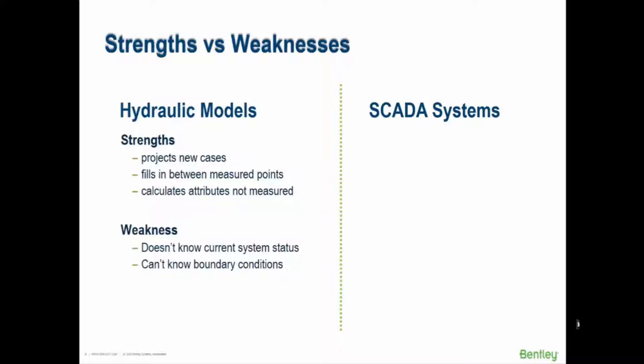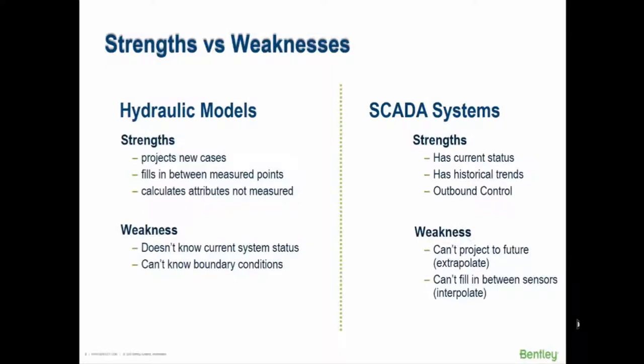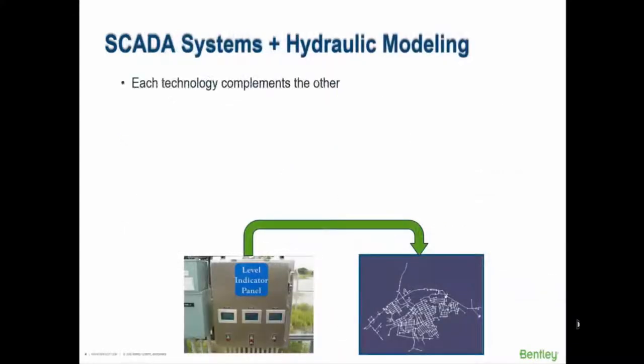The problem with models is they don't know what's going on right now, so you can't bring in live boundary conditions or initial conditions for a model run. The SCADA system, on the other hand, knows what's going on right now and what went on in the past. However, it can't project to the future, and it can't fill in between sensors — if you have 20,000 nodes in your model, you may have only 20 monitoring points. So the SCADA system and models each have strengths and weaknesses. Let's put them together and marry them.